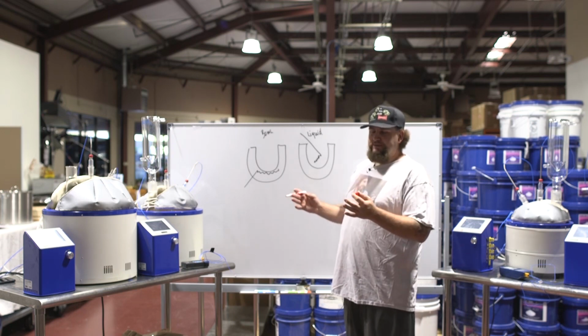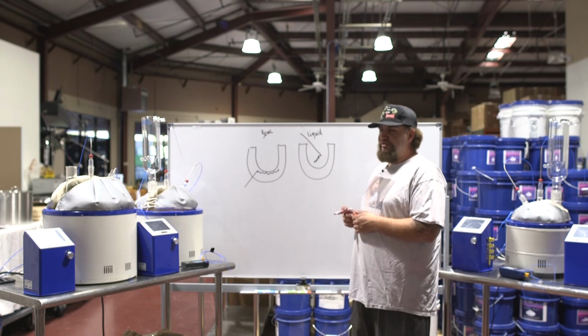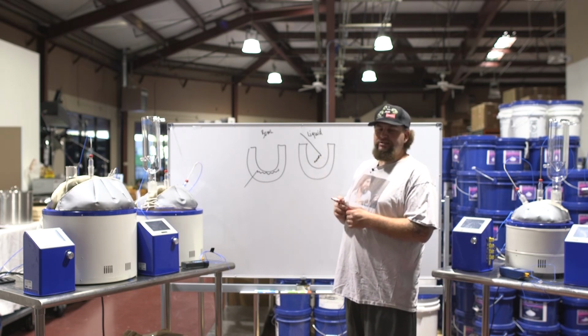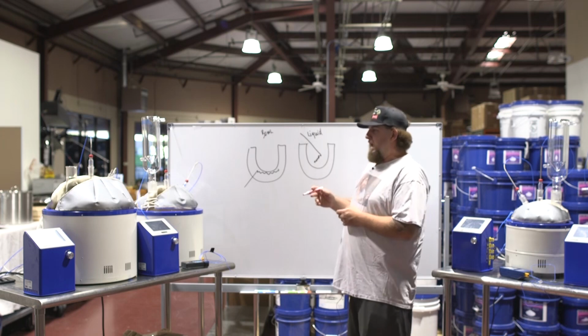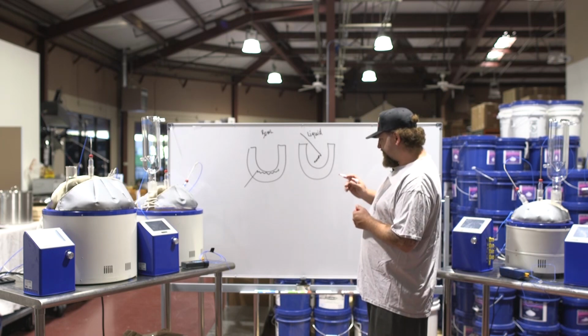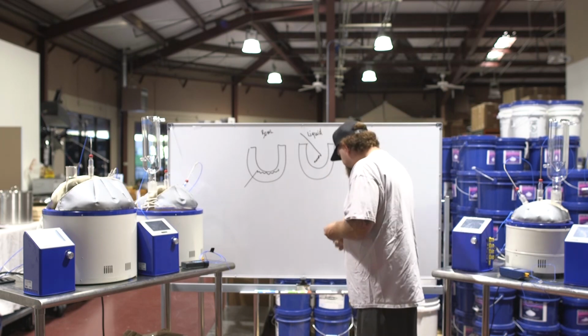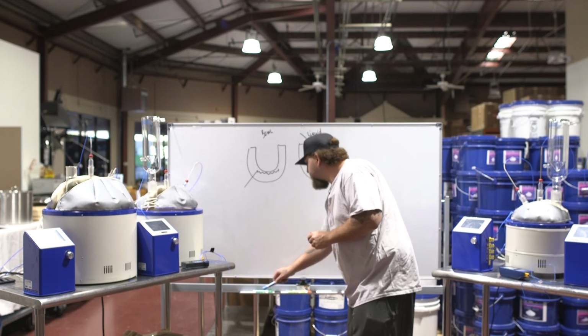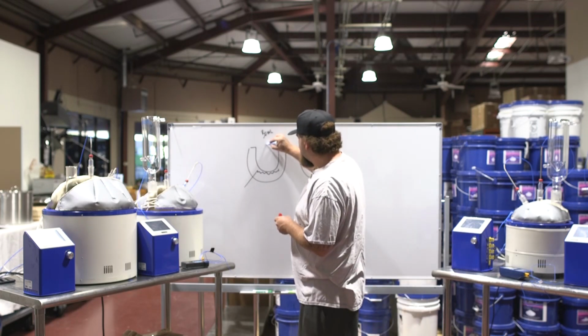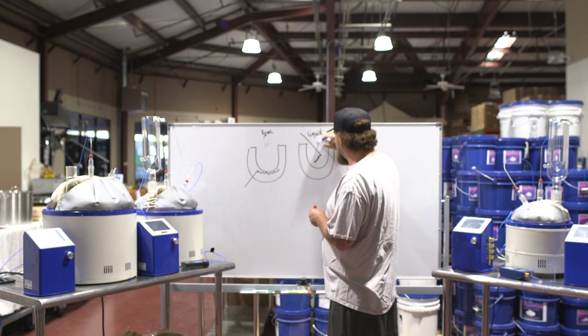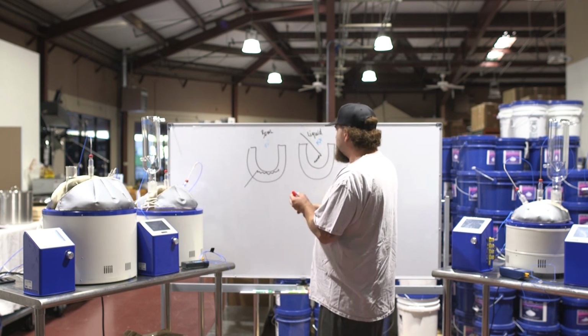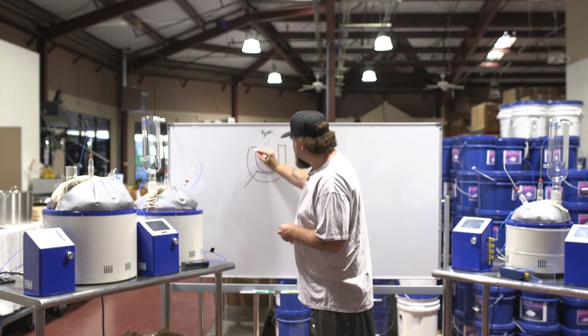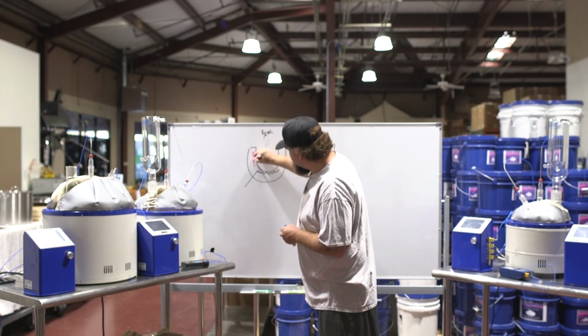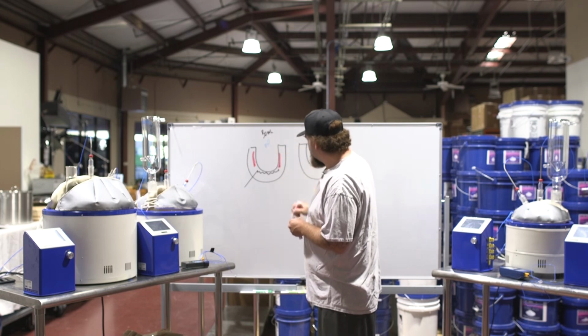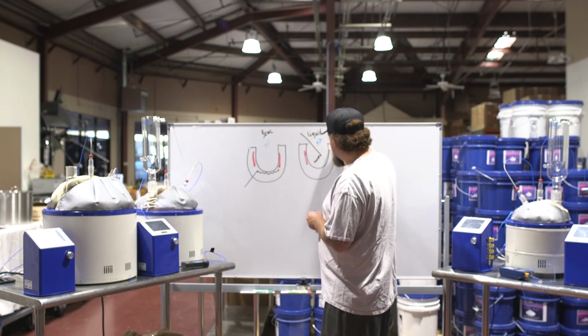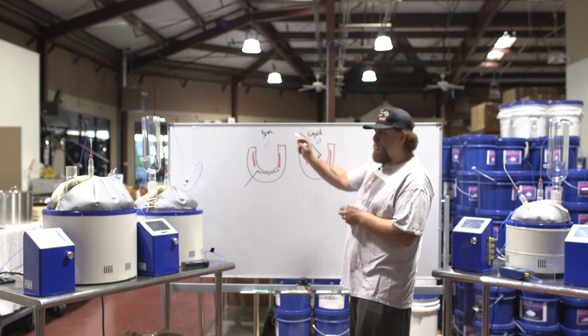So that's what brings us to the next point, is how mantles operate. Most mantles just dump heat out until it sees it at a certain point. Ours actually monitor it. And let me explain what happens first of all. So if you want to be at, let's just use this color here, 150 here and 150 on the liquid side, you're going to have heat around your mantle on both sides, and it's always going to be hotter than the 150.